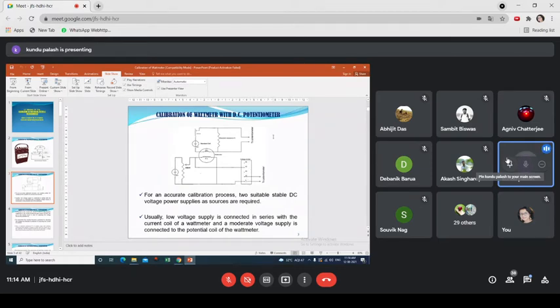Why? Because a DC potentiometer can measure only a very small voltage, about 2 volt maximum. So there is a need to reduce the potential coil voltage to a very small value by a volt ratio box, so that the final voltage is limited within the safe limit of the potentiometer circuit, that is 2 volt. Here also the voltage which is proportional to the load current is brought to the voltage within that same range.